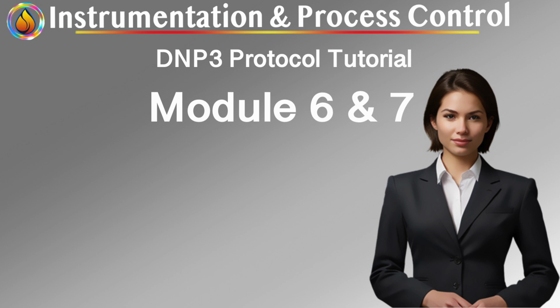7.7 Exception Handling and Error Responses. Explicit error reporting. DNP3 defines formal exception responses that indicate unsupported function codes, invalid object groups or variations, out-of-range point indices, authorization failures, resource exhaustion. Errors are reported explicitly, not inferred from silence or malformed responses. Deterministic error semantics. Each error condition has a defined response type, a defined recovery expectation. This eliminates ambiguity and prevents undefined system states.